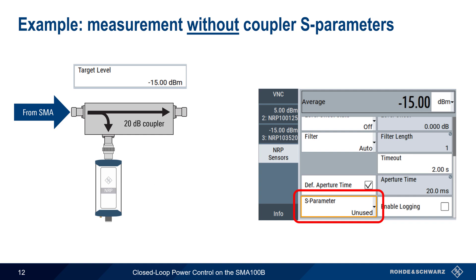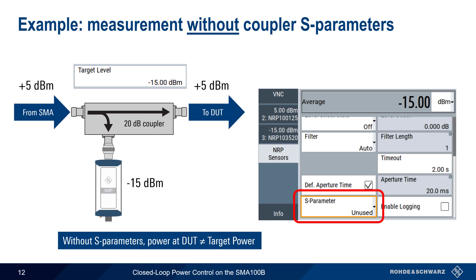Let's walk through a few examples. For simplicity, we'll assume that the SMA is directly connected to the coupler input — remember that in most cases there would be some variable gain or attenuation between the SMA and the coupler. Our power sensor is attached to the coupled port. Since here we're using a 20 dB coupler, the level at the power sensor will be 20 dB less than the level at the coupler input. If we set the target level to minus 15 dBm but do not specify the use of an S-parameter file, the sensor would read the target level of minus 15 dBm when the SMA output power is plus 5 dBm, and thus the power at the DUT would also be plus 5 dBm, assuming a coupler with typically low mainline loss. So in the case where S-parameters are not used, the power at the DUT input will not be the same as the user-configured target power.